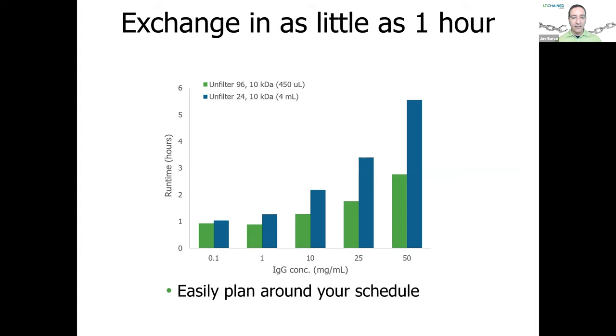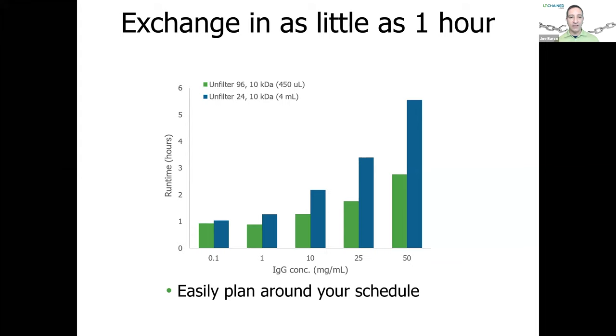This is relatively fast — I can exchange 96 samples at low concentration in under an hour. As protein concentration increases, viscosity increases, which slows down flow on any method. Even at about 50 mg/mL in a higher volume on the 24-well unfilter, we can still finish in six hours — fully unattended — and at higher quality than you would get from a centrifugation filter. You can also run overnight if you're not running at higher protein concentrations.